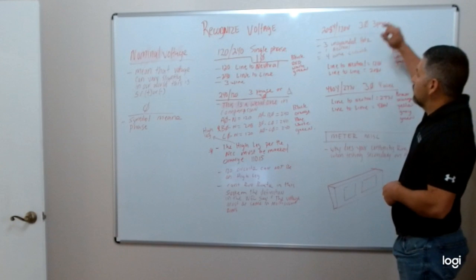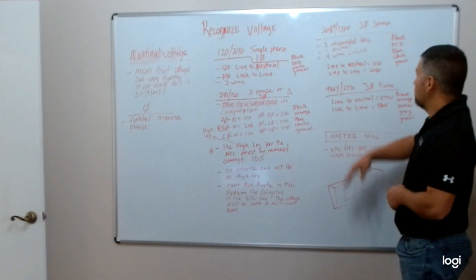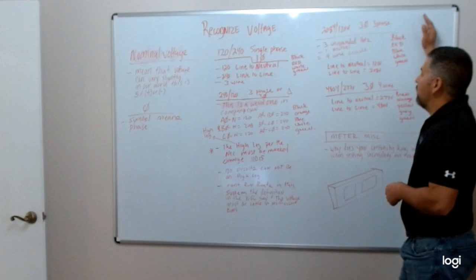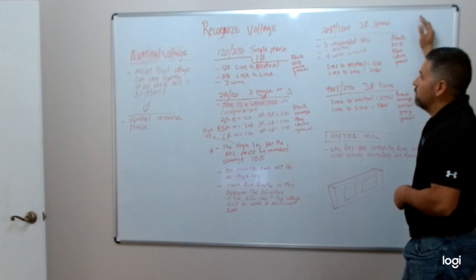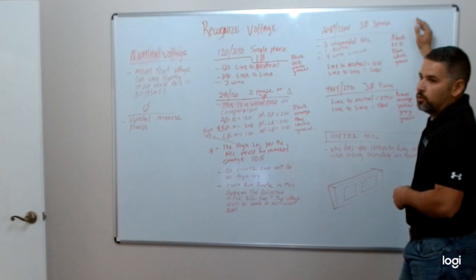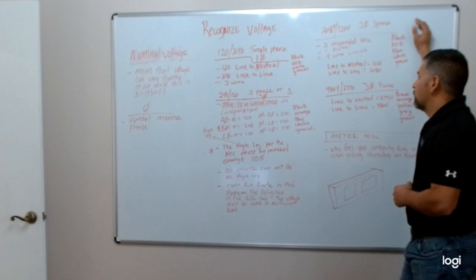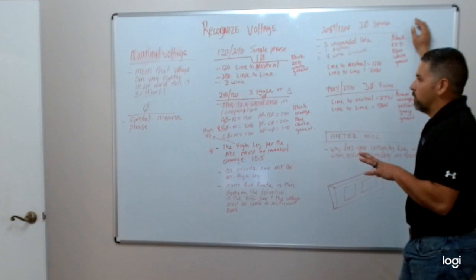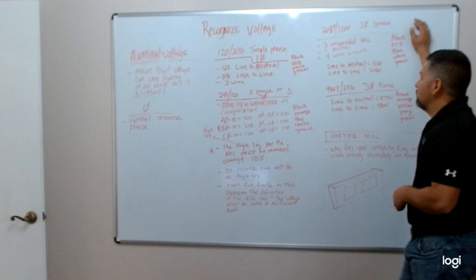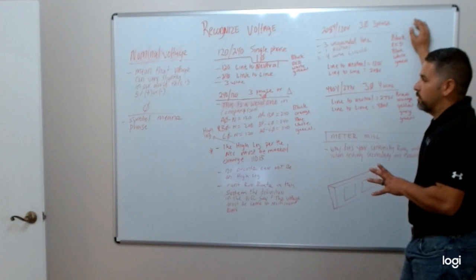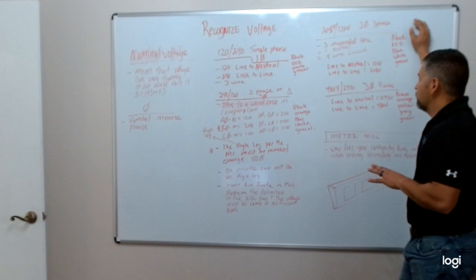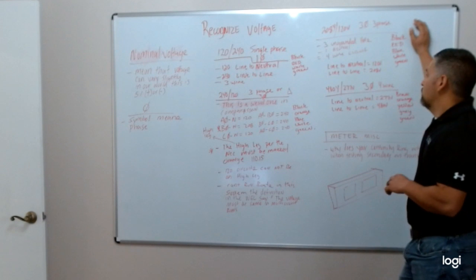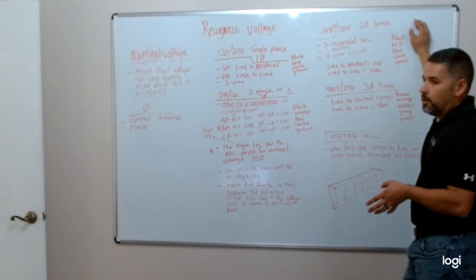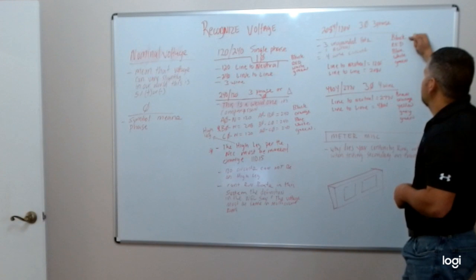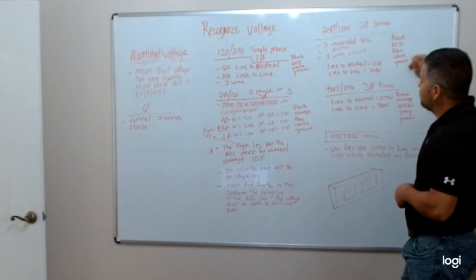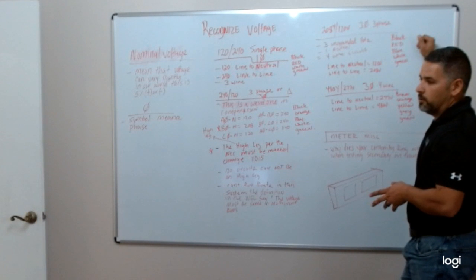So that's the crazy leg. Our next system is more common. It's going to be the 208 120. This is going to be in your normal commercial panel. It's 3 phases, so 3 ungrounded circuits, 1 neutral, so a 4-wire circuit. Line to neutral is going to be 120. Line to line is going to be 208. Black, red, blue, white, green is going to be your color combination for us.